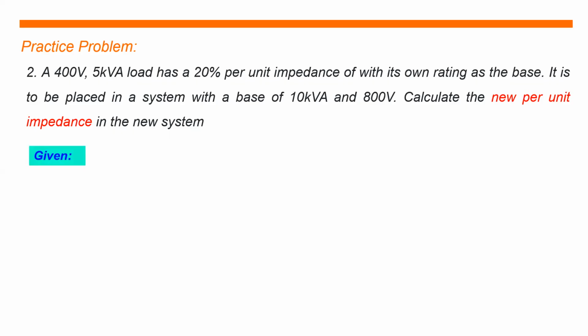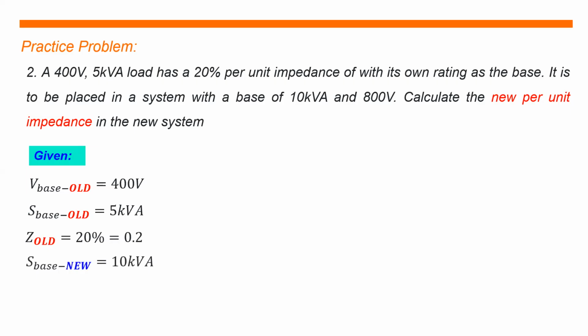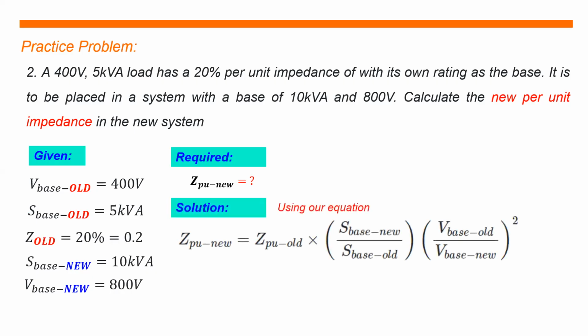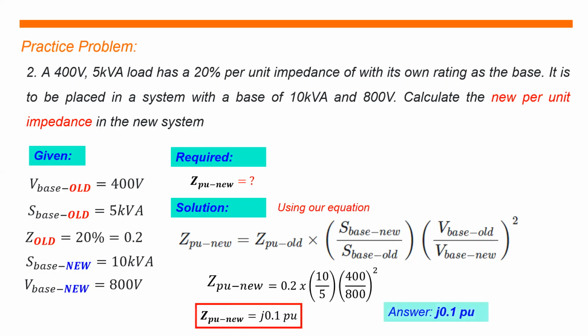So again, let's write all the given values. We have the old base voltage, which is equals to 400 volts. The old base power is equals to 5 kVA. The old impedance, which is 20%, which is equals to 0.2. And the new base power is 10 kVA. The new base voltage is equals to 800 volts. So we are asked to solve for the new per unit impedance. And again, using our equation, we will just substitute all the given values to our equation, and then we will get the value of the new per unit impedance, which is equals to j0.1 per unit.